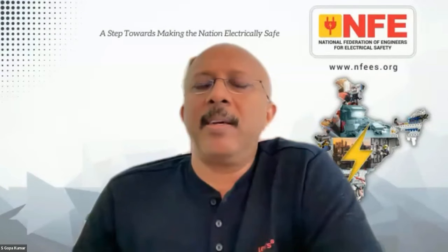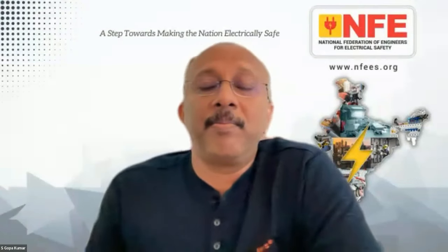I just wanted to add something. So the standard Mr. Vajari is referring to, I think it's referring to the fact that you shouldn't use a gas pipe, a steam pipe, a sprinkler pipe, or a humidifier as a means of earthing. So that's as an electrode. That obviously you're not supposed to do in any case. So that's similar to what 7671 says as well. You're not supposed to use those as an electrode. Yes. No, you shouldn't be. Or they'll be done by default. Potential bonding anyway. Yeah.